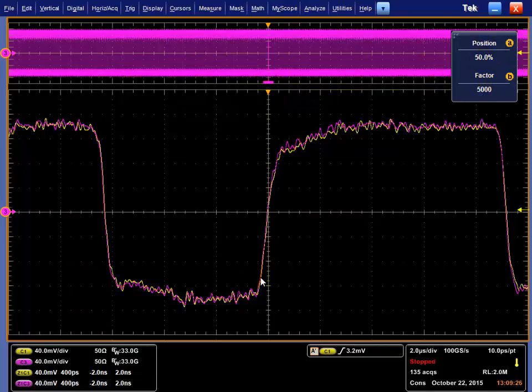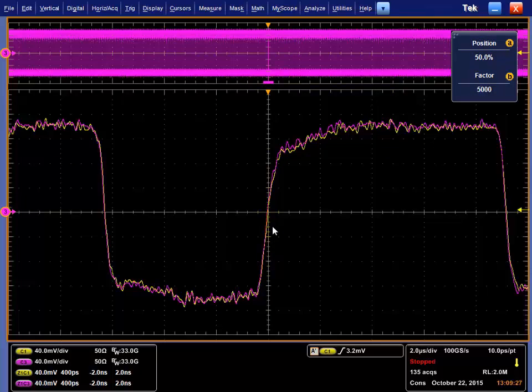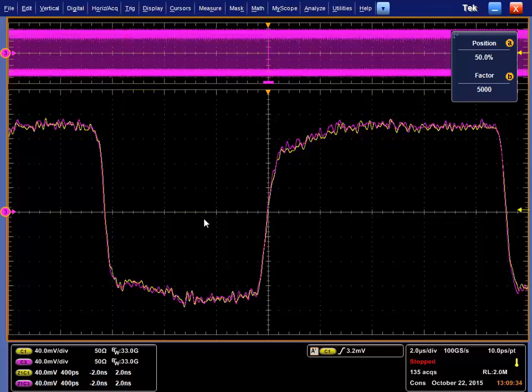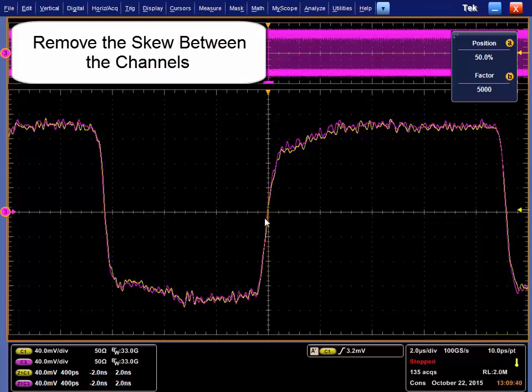I'm zoomed in to look at this waveform, and we're going to look at the skew, because now we're satisfied that we're doing decent. We've got 80% of the screen full vertically. We've got a good high sample rate, and we've captured a long record length. So now we need to check the skew.